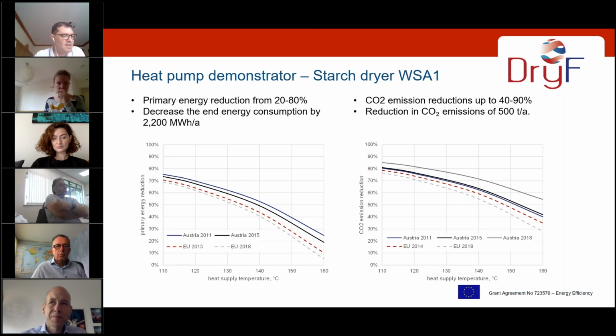On this slide, you can see the expected targets of primary energy reduction and CO2 emission reduction as calculated at the start of this project. So the primary energy could be reduced, depending on the heat supply temperature, by 20 to 80%, which would lead to around 2,200 megawatt hours per year in energy consumption savings. And concerning the CO2 emission reduction, it could be up to 40 to 90%. In this case, it could lead to a CO2 emission reduction of approximately 500 tons per year, depending, as I said, on the heat supply temperature.